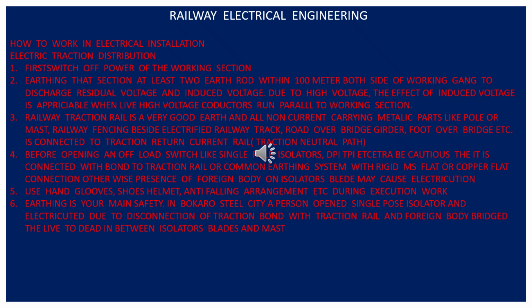So after this isolation you have to provide earthing, at least with a discharge rod or earth rod, because there are multiple lines, up and down lines. One line may be switched off, but the other line will be energized. So the induction effect on the dead OHE, if you touch it, is enough to electrocute. So be cautious. Though your section is dead, if it is without earth, it can be almost live, around 2 kV, from the live overhead conductors of the other track line. So be cautious, provide earthing.